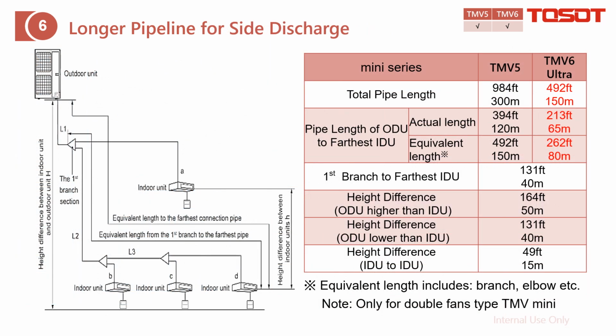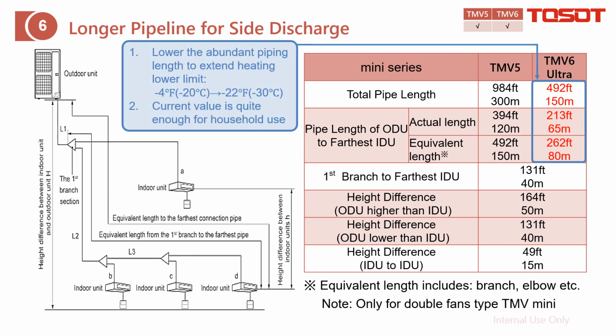As for side discharge, this time GMV6 compared with GMV5 has only half the value, either for the total piping length or from the outdoor unit to the farthest indoor unit. We just ensure the height difference is the same. The reason is that we focus on extending the operating range from -4 to -22. We focus on this, so we sacrifice some piping length, because for household use this value is quite enough.